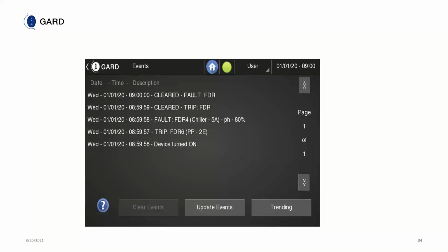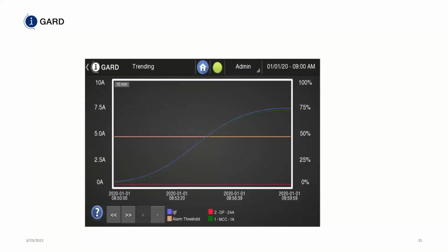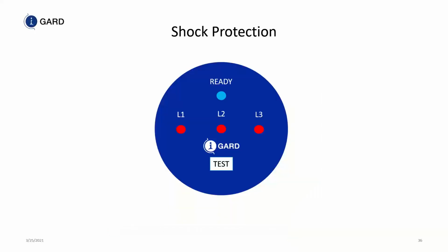We tell you any of the history that occurred, a fault occurred, a trip occurred, and trending. So you can actually trend a line, a feeder, and determine how it's doing and if it's trending to be more deteriorating than others, because you'll see this time period change and you have selectability over this time period. So this could be like 2 years and you can see it changing and determine if you need to act or not. So this is basically maintenance by exception as opposed to routine maintenance.